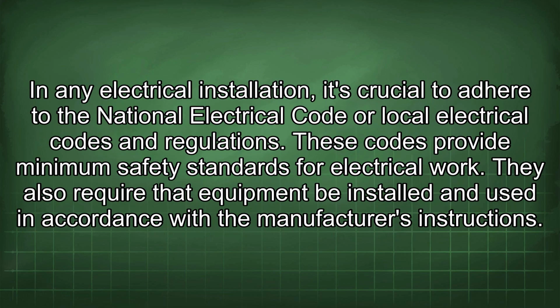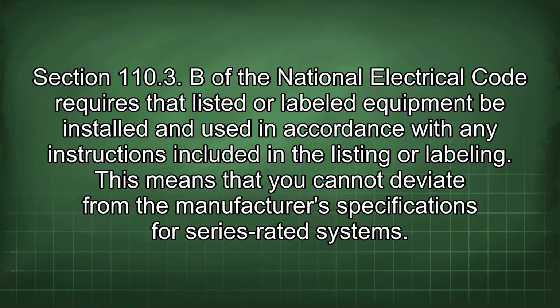In any electrical installation, it's crucial to adhere to the National Electrical Code or local electrical codes and regulations. These codes provide minimum safety standards for electrical work. They also require that equipment be installed and used in accordance with the manufacturer's instructions. Section 110.3(B) of the National Electrical Code requires that listed or labeled equipment be installed and used in accordance with any instructions included in the listing or labeling. This means that you cannot deviate from the manufacturer's specifications for series-rated systems.